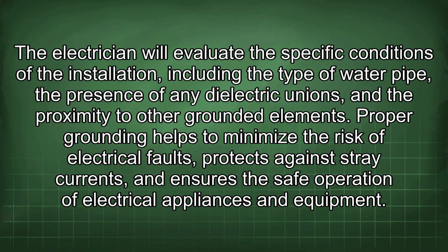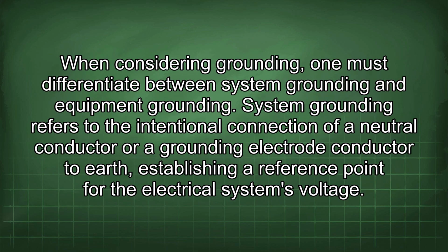The electrician will evaluate the specific conditions of the installation, including the type of water pipe, the presence of any dielectric unions, and the proximity to other grounded elements. Proper grounding helps to minimize the risk of electrical faults, protects against stray currents, and ensures the safe operation of electrical appliances and equipment. When considering grounding, one must differentiate between system grounding and equipment grounding.